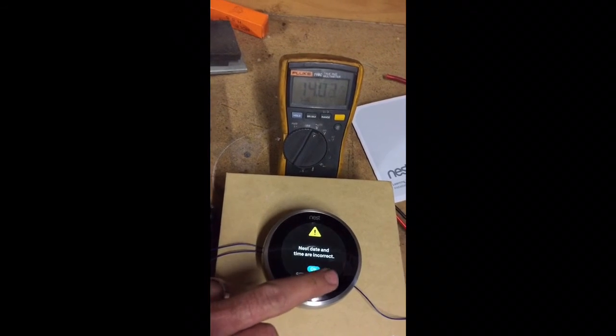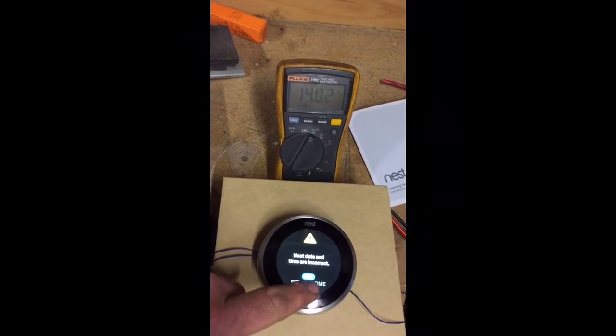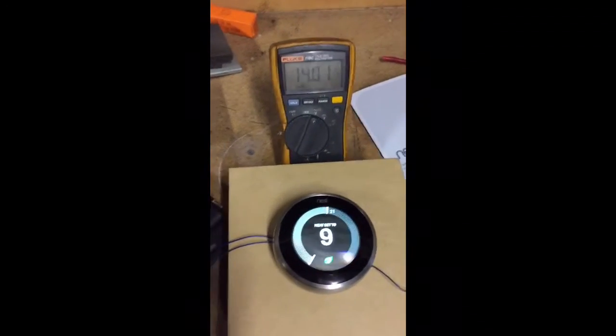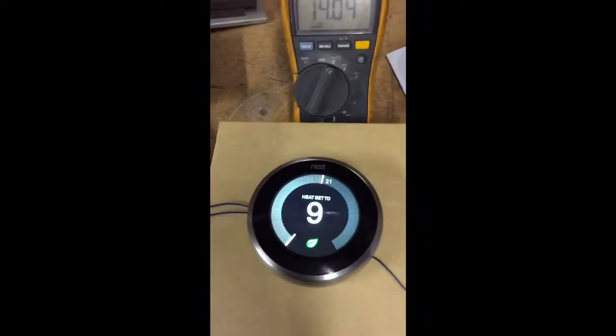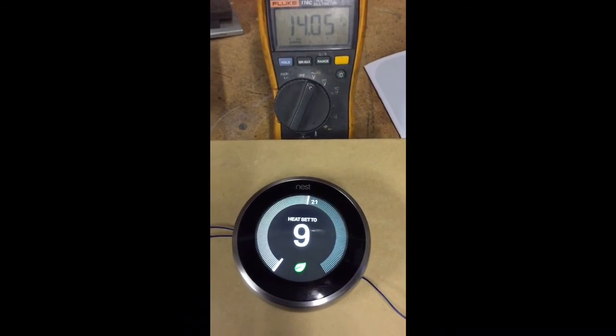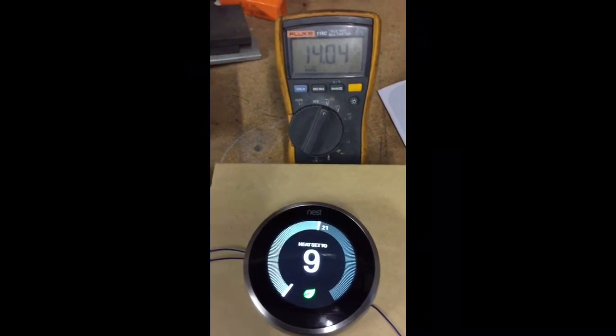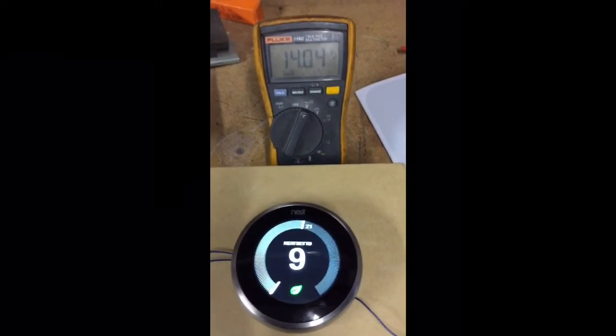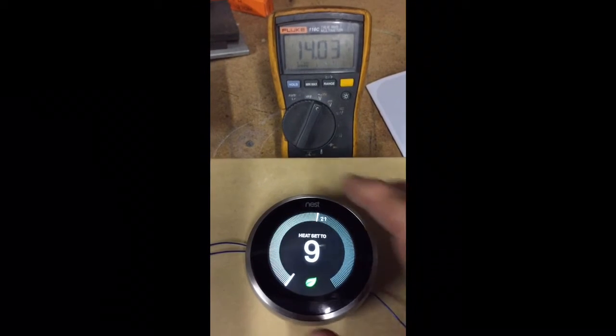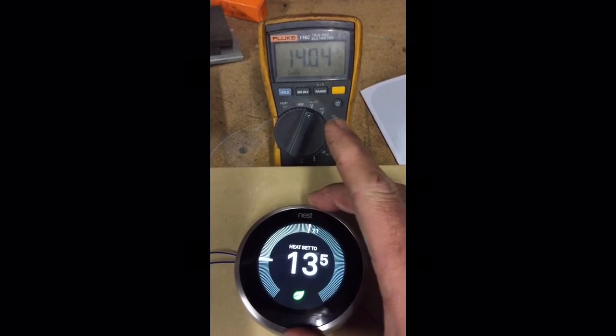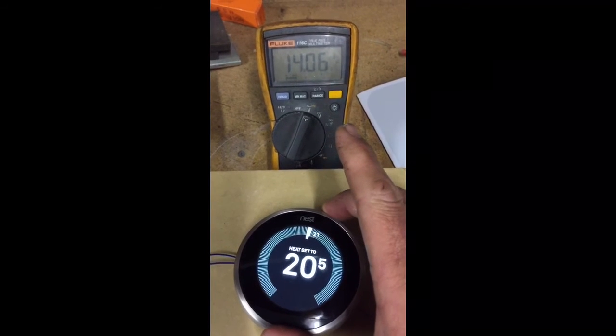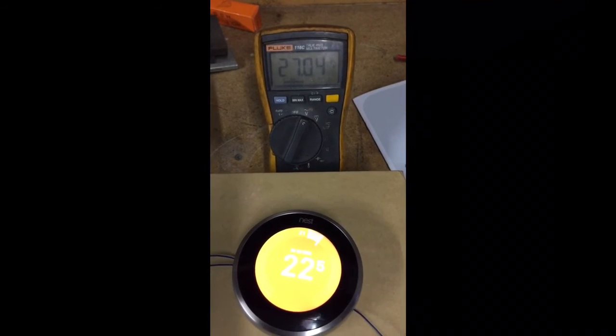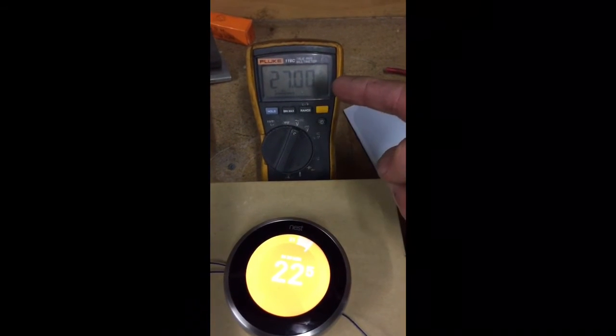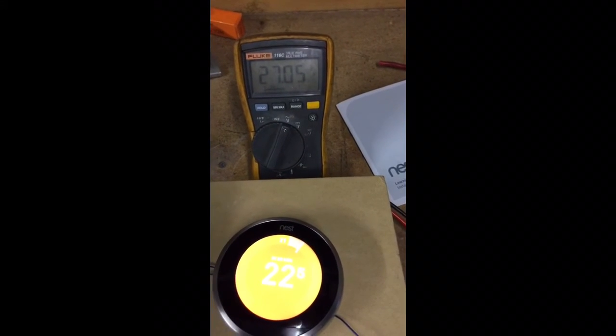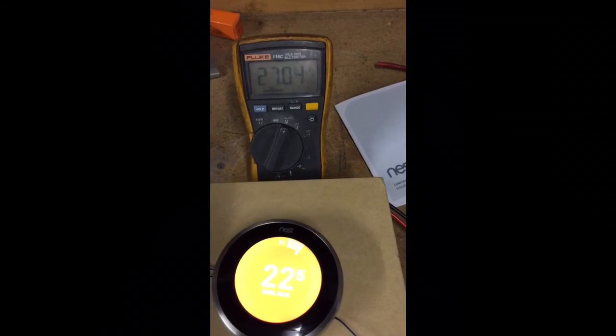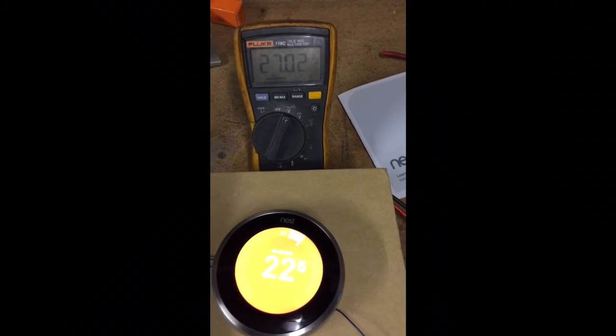Alright, so we don't need to set the time there, so we'll just bypass that for the moment. The controller is saying there that it's 9 degrees set point, and the room temperature at the moment is 21 degrees. So to bring this unit up into heating, we've got to get above that set point of 21. So we'll just give that dial a turn up. We'll get it above the 21 point, and then the unit will go into heating mode. The screen goes red to indicate we're in heating mode, and as you can see on the multimeter here, we've now got 27 volts output. So that should then go out and switch the gas valve and start the heating cycle up.